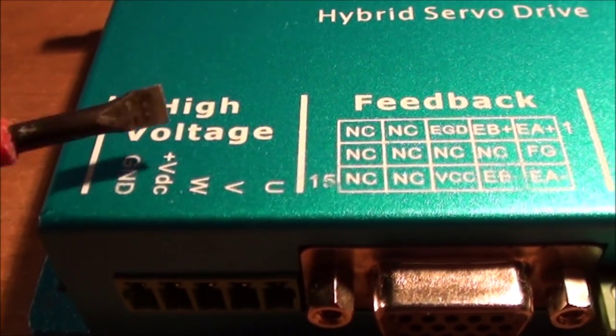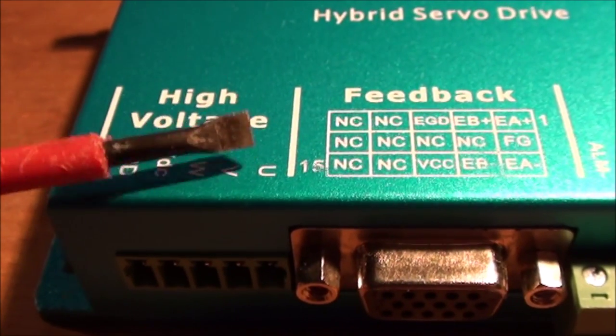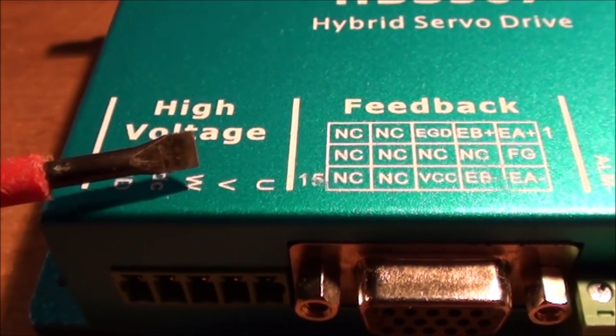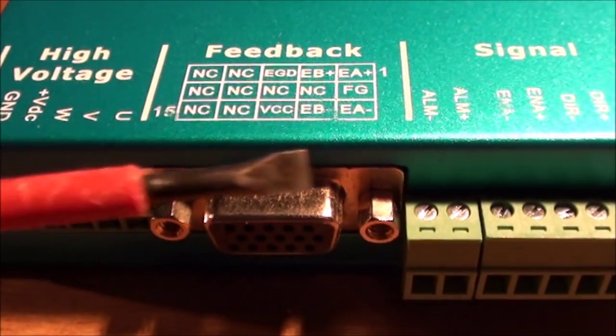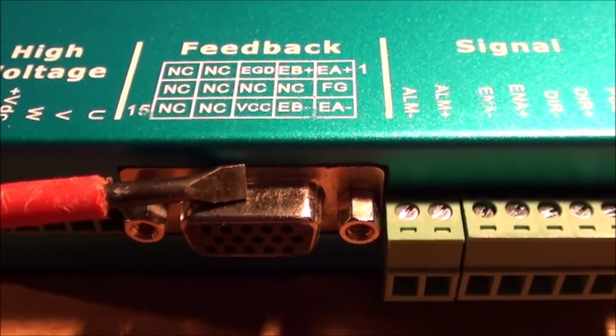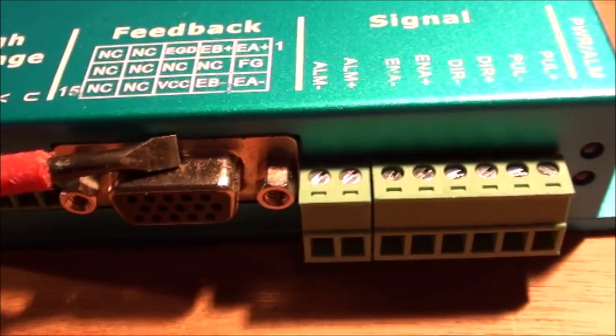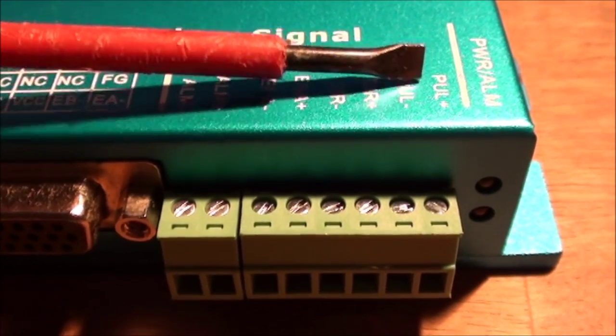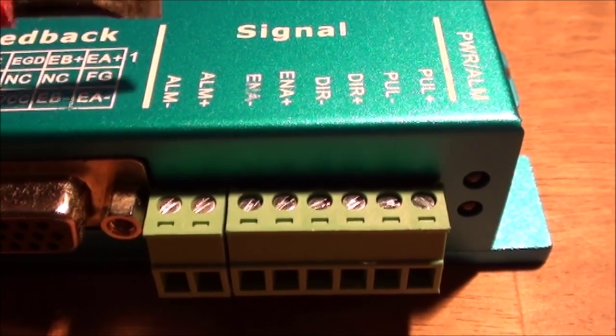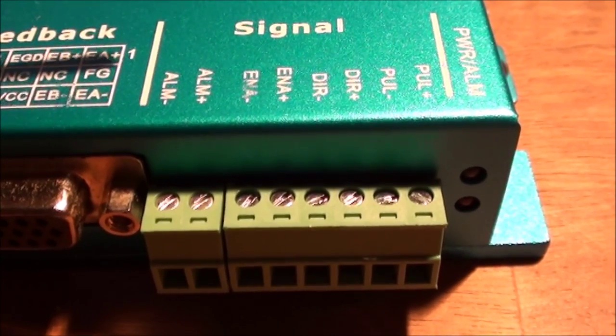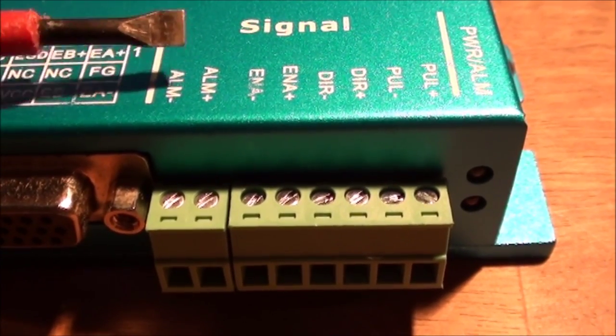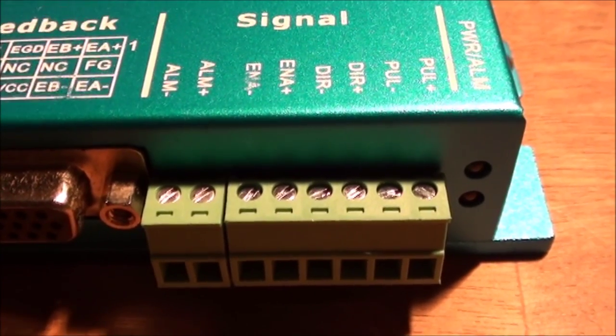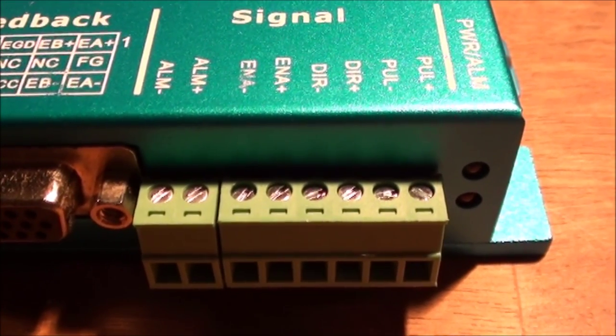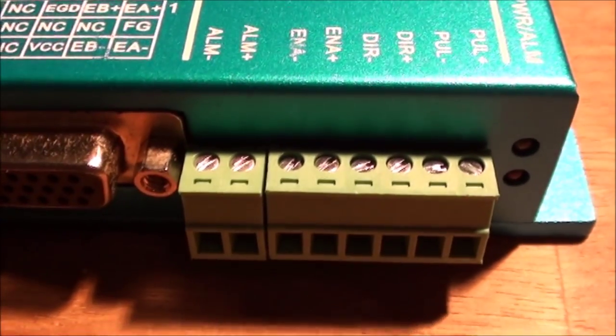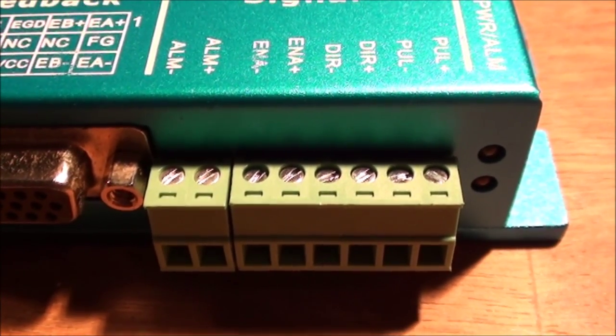So here you can see you have a couple of connections for the power, U, V, and W. That's for the motor because it's an AC motor. Then you have this DB15, which is for the encoder. I'll show that in a second. And then you have the normal pulse, direction and enable, and then there's also an alarm that you can connect if you like. It will make an alarm if you go outside the limits of the motor that you have set.